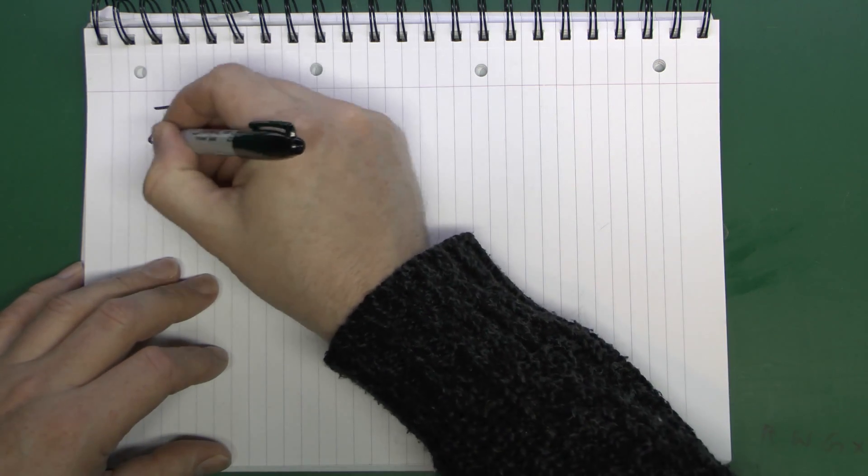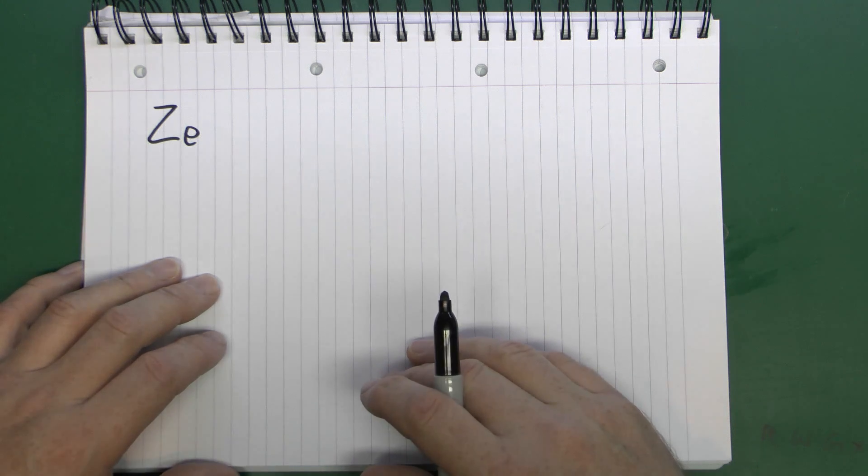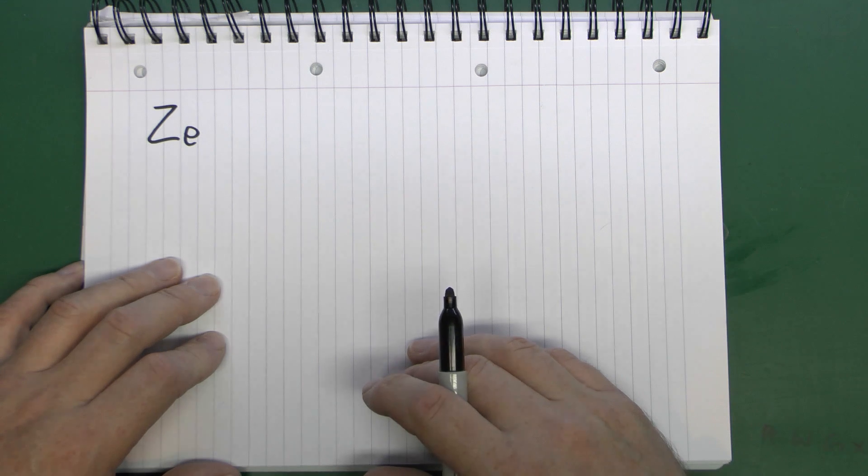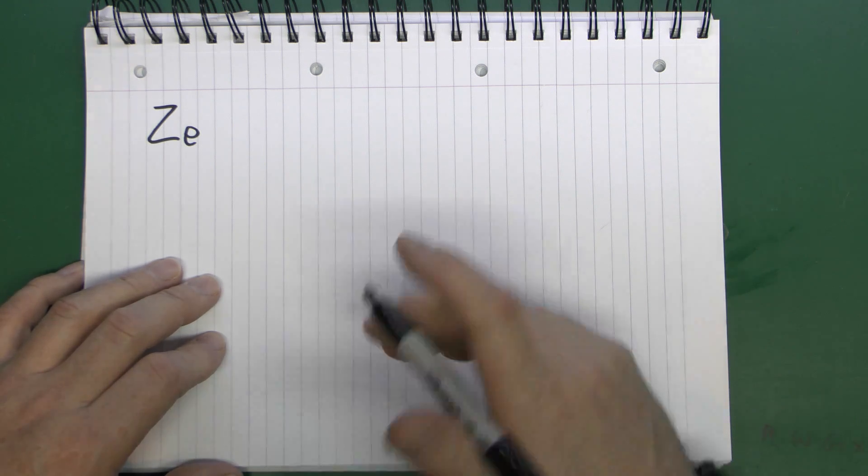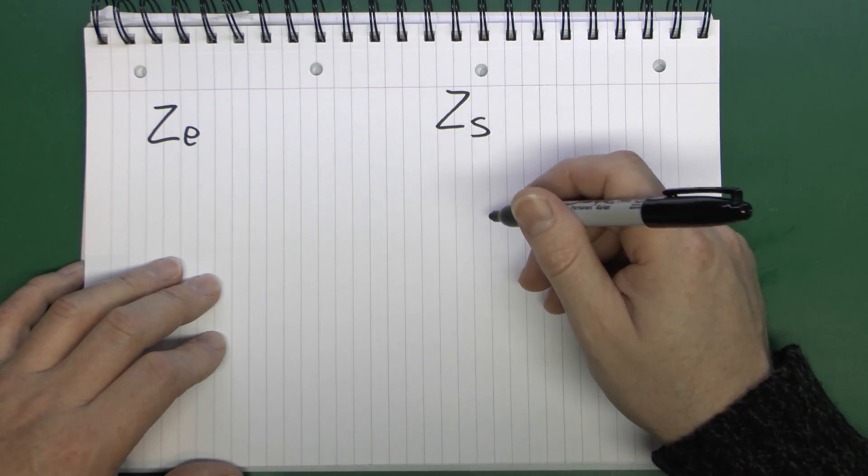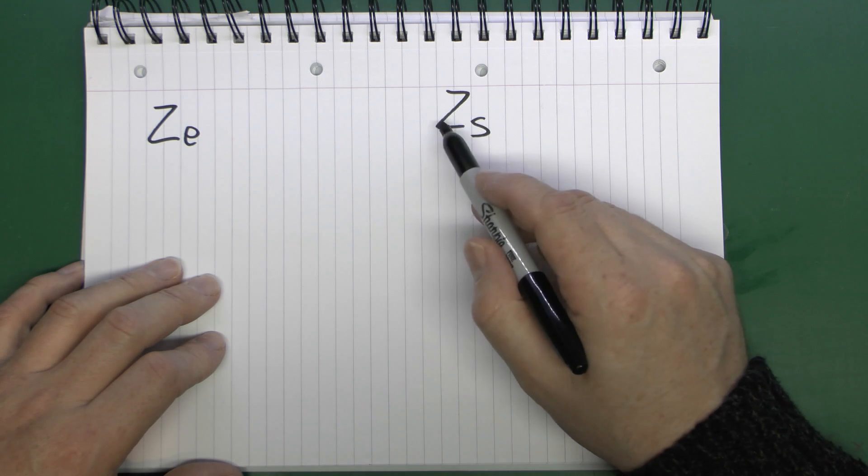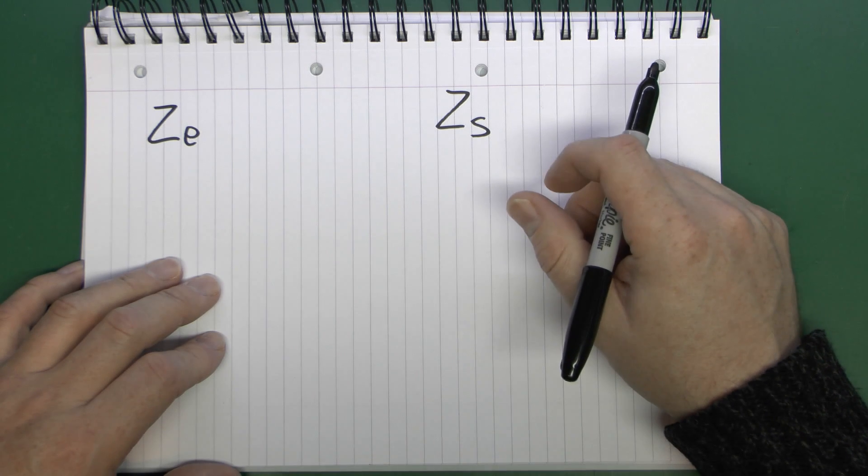Now in the case of this test we're actually concerned with the external earth fault loop impedance and this is typically given the symbol Z for impedance and then E and E for external. So this is purely the effectiveness of the earth connection being provided to the building and does not involve the circuits within the building at all. You can test the circuits inside the building, that would be given the symbol ZS, which is done at the end of each circuit. It's just the resistance of the circuit wiring added to the external loop impedance.